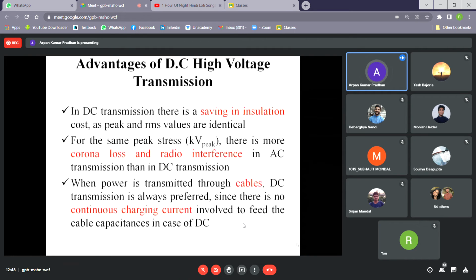Due to this corona, power loss will occur in the transmission line, and it can also interfere with other radio signals. If you consider the DC system and AC system, in case of AC, as the peak value is higher than the RMS value, the corona loss will be higher in the AC system. But in case of DC, as it has a steady value, its corona loss will be lower. Similarly, radio interference for the AC system will be higher, whereas for the DC system it will be lower. So this is another advantage of using a DC high voltage system.